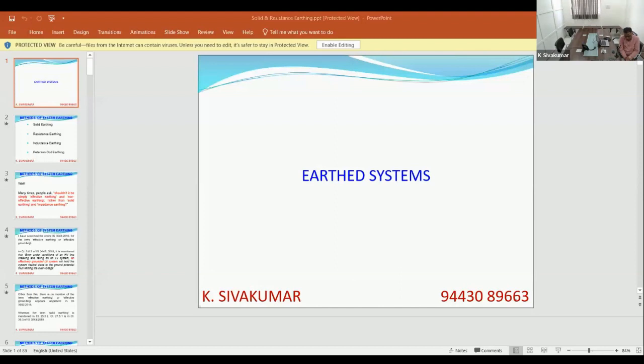Yeah, I have written to BIS, they say they are reviewing and the next edition should be corrected. So many things still need to be corrected. Maybe we can contribute and give our inputs to BIS. We have taken up the next revision of IS 3043, and I think we have to look into this subject seriously. The question is, where is the proof? For example, at the moment the corrosion allowance given is, let's say, 20%. If more is required for an area where the soil resistivity is less than, let's say, 20 ohm meter, where is the study report? Sufficient reports are not there.